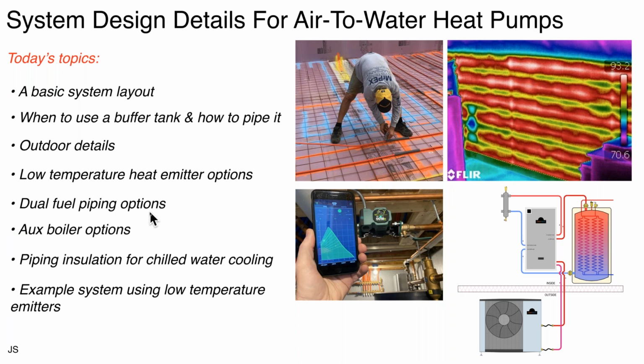And of course, one of the advantages that heat pumps have over boilers is that they can produce chilled water, so we can do chilled water cooling systems. And it is important when you're doing chilled water that you respect insulation on the pipes and vapor sealing, to make sure we don't get condensation forming where we don't want it. And then I'll finish up.